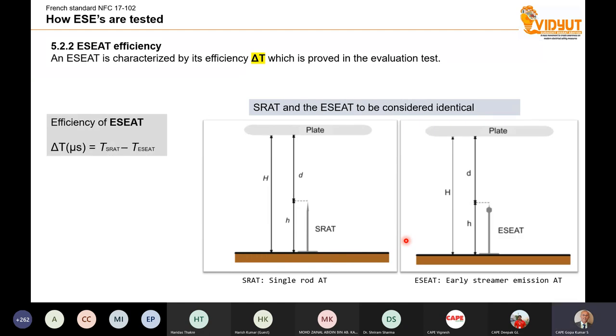Now, what do they do with respect to the testing? Delta T, how do they find out the delta T? Imagine you have a laboratory, and in the laboratory, first you test a single rod air terminal. That means a normal iron rod, maybe 1 meter height. And then at the top, there is a plate. At the bottom, there is again another plate. Between these two plates, a charge is created. Once the voltage goes beyond a certain limit, a breakdown happens. So they make a breakdown. And the time with which this particular device is emitting some kind of early streamers is taken, and this is called the time of the single rod air terminal.